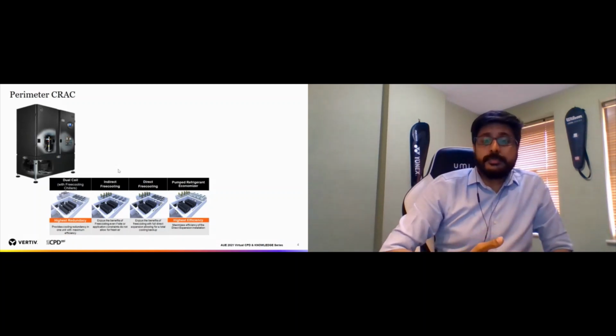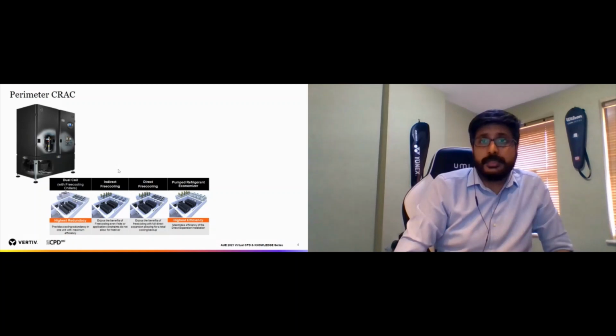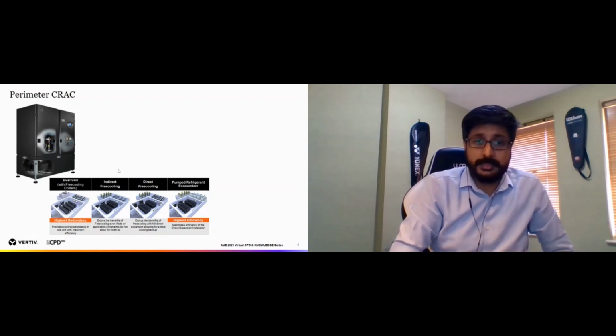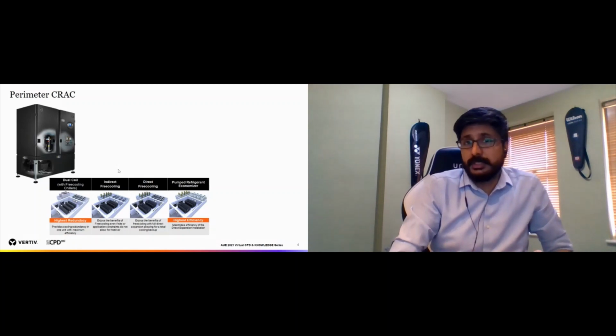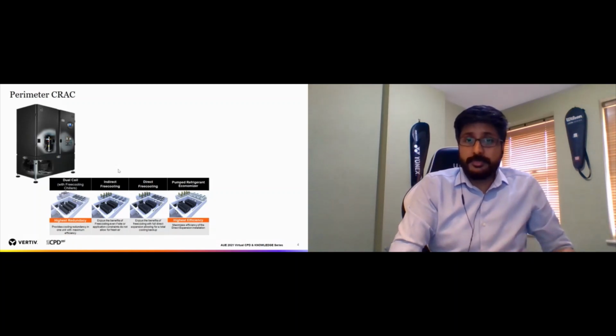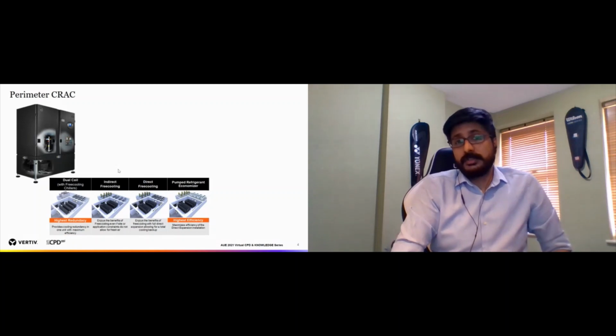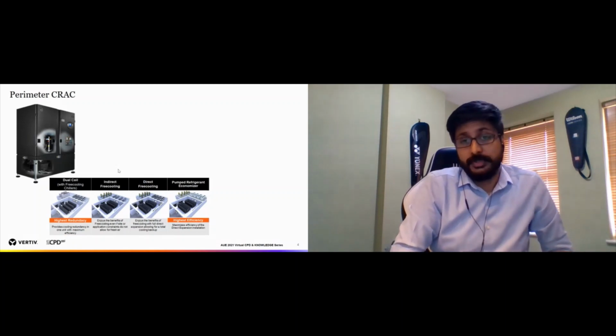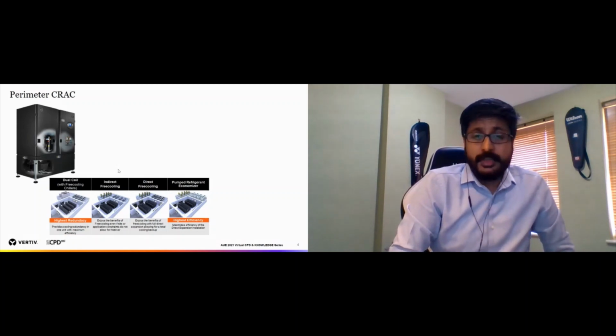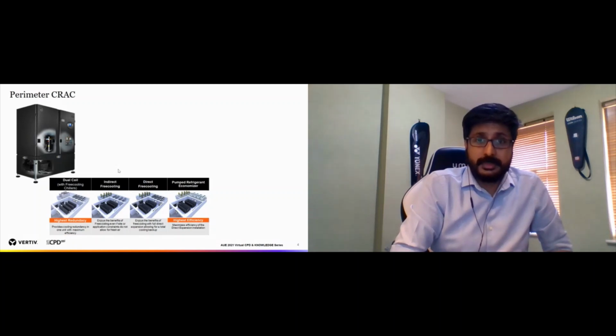The next stage, to get the highest amount of efficiency, is a system called a pumped refrigerant economizer. You need to run a compressor when the temperature is really high, but if the external temperatures are favorable, we don't need a compressor to raise the refrigerant temperatures. We can just have a pump to provide the mass flow in the system. So the compressors can be switched off, pumps can be turned on, and the external condensers become just like a free cooling refrigerant coil, let's put it that way. That means we get the highest amount of efficiency, because the highest power consumption is the compressors, which are switched off, and we are running small pumps, which are minuscule in terms of power consumption. As a rough estimate, we're seeing around 60% efficiency gains when you use these pumped refrigerant economizer systems.